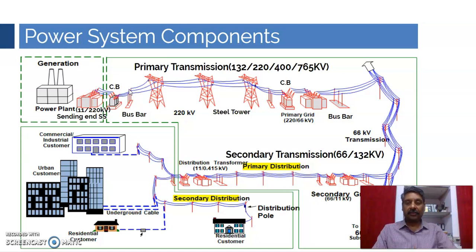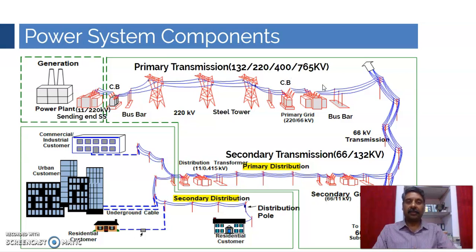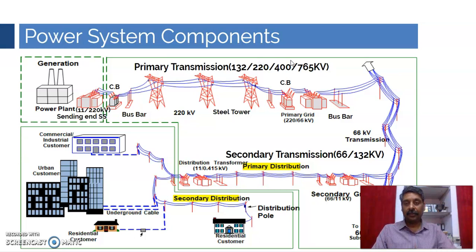From the substation we have circuit breakers, bus bars, and then that is connected to the transmission line. In the Indian scenario, transmission voltage levels start from 132 kV, 220 kV, 400 kV, and 765 kV — all AC transmission lines. In addition, we also have 500 kV HVDC as well as 800 kV HVDC, and we are now planning for 1200 kV AC at the transmission level. The network at 132 to 765 kV AC is called primary transmission.